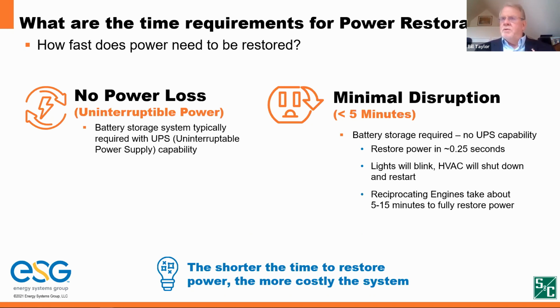If you have minimal disruption, say less than 5 minutes, you probably will have another battery, but it won't be uninterruptible. It'll be a slightly different inverter with a different function. It'll recognize the voltage drop and come online in probably a quarter of a second, but enough of a time lag will exist where the lights are going to blink. HVAC may restart. You're going to have some notification that, hey, the power just went off.